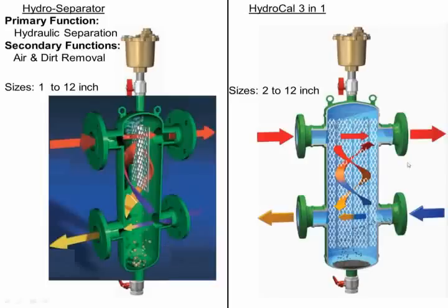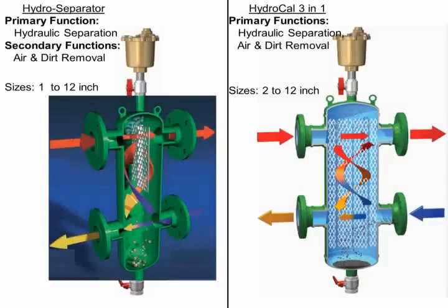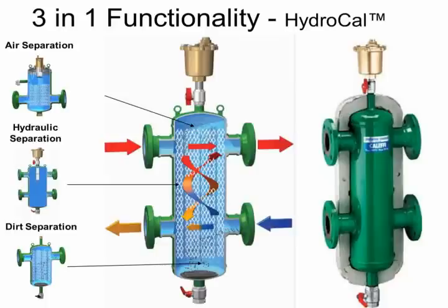However, we introduced a couple of years ago another line of related product. It's a hydro separator where we pulled out the baffle plate, and throughout the internal part of the separator, we have included a coalescing mesh, okay, a little bit differently designed. And as a result, we get high efficiency air elimination by coalescing. We have the same level of dirt elimination capability as a dedicated dirt separator, and we get hydraulic separation. So all three functions are available in the HydroCal.